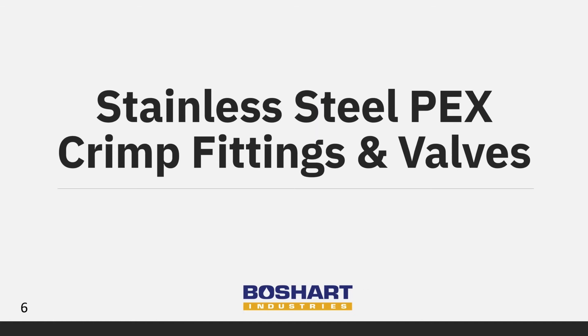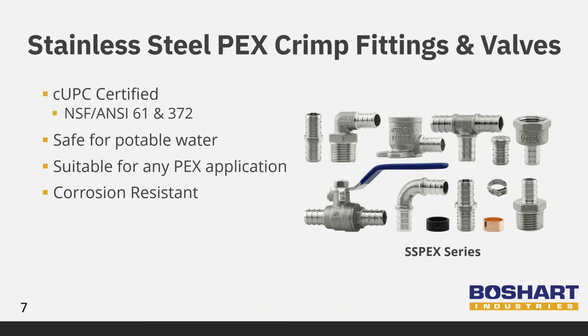We started receiving shipments of the new fittings and valves and we're very excited about them. Boshart Industries is first to the market to offer full stainless steel PEX crimp fittings that are CUPC certified to NSF ANSI 61 and 372. This ensures that they do not contain lead or other toxins, making them safe for potable water. The chemical compatibility and superior corrosion resistance of these 304 stainless steel fittings make them suitable for plumbing, hydronic heating, and a wide range of specialized applications.